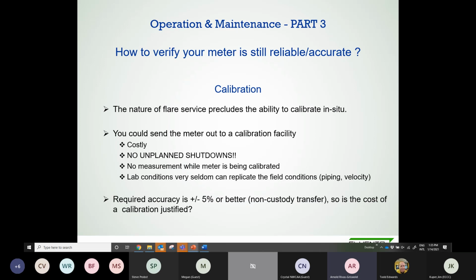So when it comes to flare measurements, it's really tricky because in many applications, you can get up to 300 or almost 400 feet per second in velocity in an emergency situation. And I'm talking about a very significant volume in terms of the facility capacity, right? But at the same time, the meter has to be able to go down to 1 meter per second or less. Because it's really difficult to replicate those kinds of velocities in the field, the question is, if you're going to calibrate it, what do you calibrate it for? Because in many cases, you don't really have a good reference that can go that high in terms of velocity.